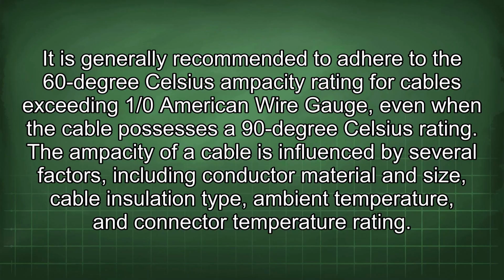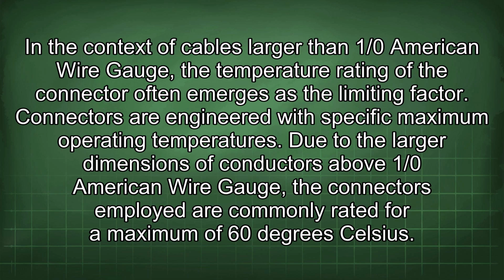It is generally recommended to adhere to the 60 degrees Celsius ampacity rating for cables exceeding 1/0 American wire gauge, even when the cable possesses a 90 degrees Celsius rating. The ampacity of a cable is influenced by several factors, including conductor material and size, cable insulation type, ambient temperature, and connector temperature rating. In the context of cables larger than 1/0 American wire gauge, the temperature rating of the connector often emerges as the limiting factor.